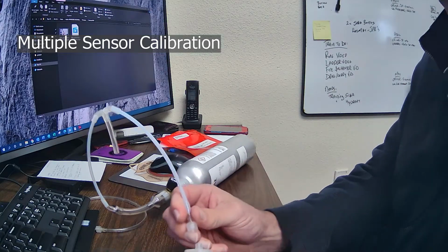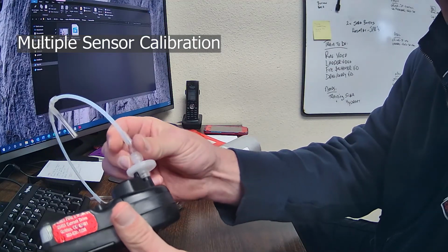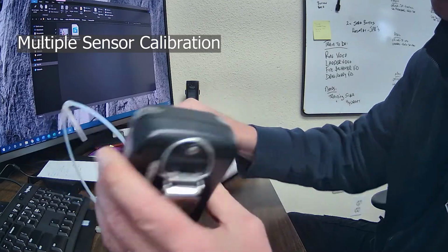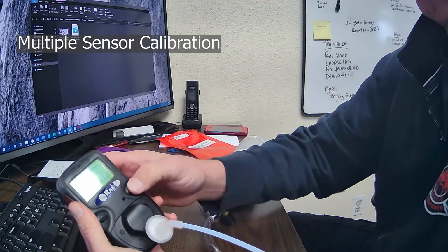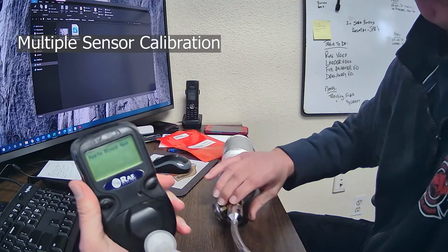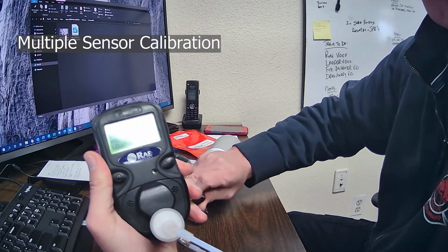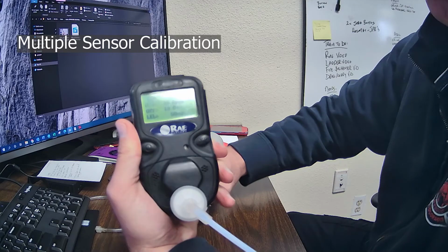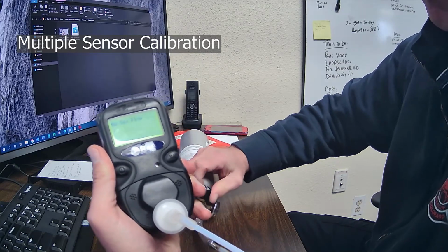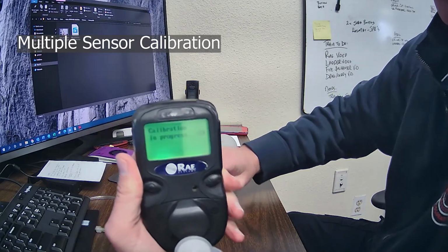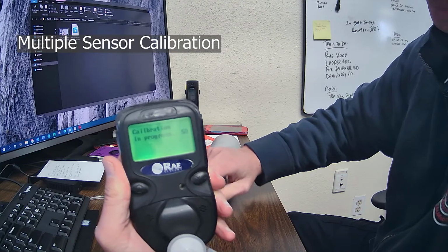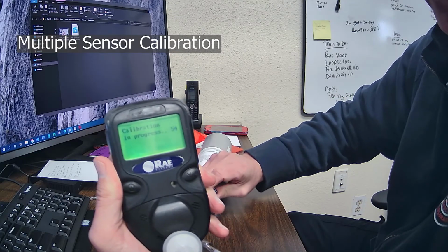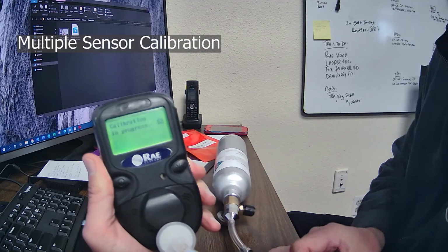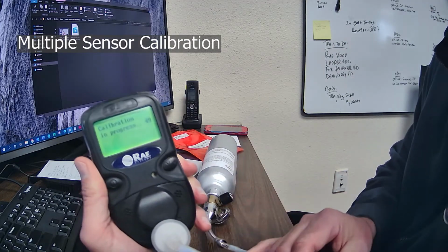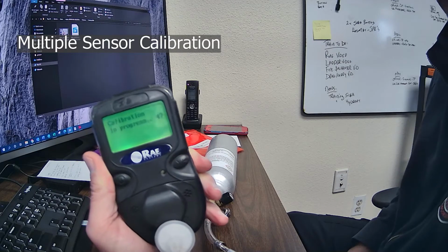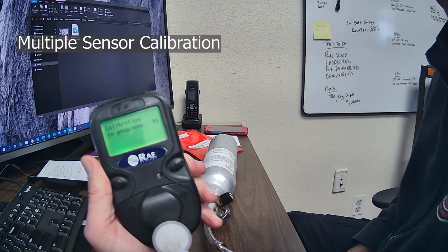So now you take your adapter tube. It goes right on top of your filter. It's not going to read anything. We're going to go ahead and say OK. And then it says apply mixed gas. We did that. And then all you have to do is turn it on. You open it. And it's going to go through the calibration. So we got 50, 57. This takes a minute, so it's a little bit longer. Open it all the way up. And you can hear it blowing off. So we're going to lose a little bit of gas, but that's okay. We won't lose the 4-gas meter.